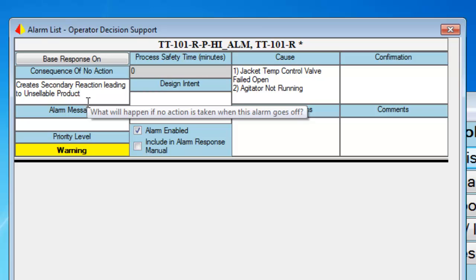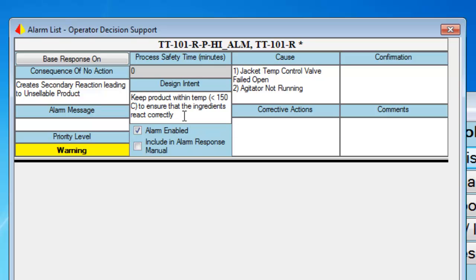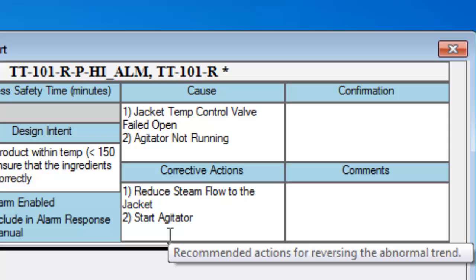For our reactor high temperature alarm, the consequence of inaction would be the creation of a secondary reaction leading to unsellable product or loss of product. Next, we want to define and document the design intent or purpose for the alarm — for our reactor example, to prevent a high temperature from occurring as this would lead to unsellable product. One of the most important tasks during alarm rationalization is to define what the operator's corrective action should be. We don't mean just acknowledging the alarm; we want actions that would correct the abnormal situation, like starting a pump or opening a valve. If we can't define what the corrective action should be, then the point should likely not be an alarm.